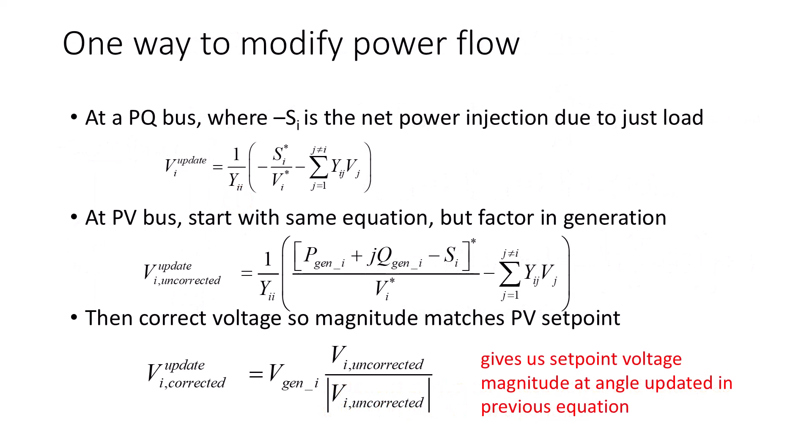In the three bus power flow example, when we just had to find voltages at constant power PQ buses, we updated the voltage using the formula shown here. The bus net current injection is estimated by taking minus S conjugate divided by V conjugate, where S is the load power and V is the last estimate of the bus voltage. At a PV bus, we use a similar update formula.